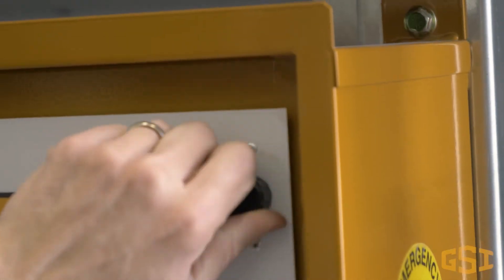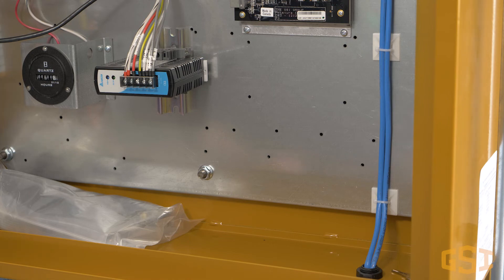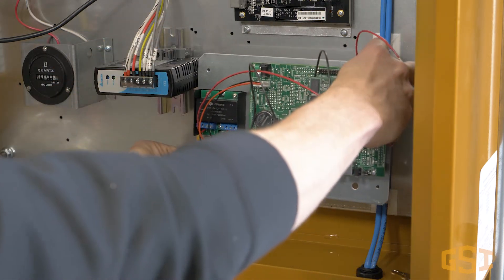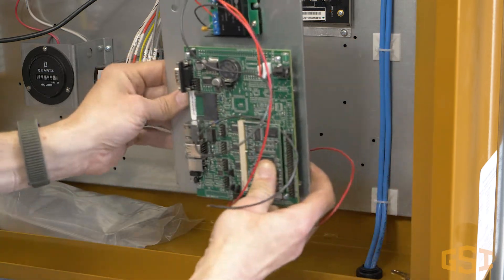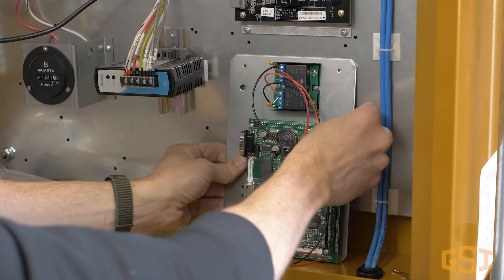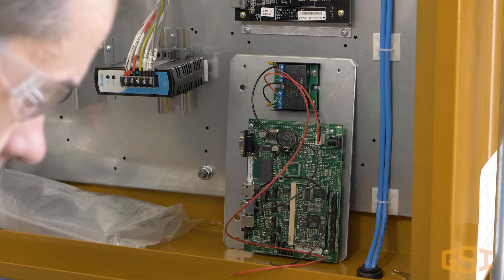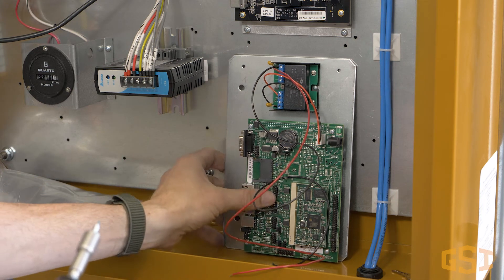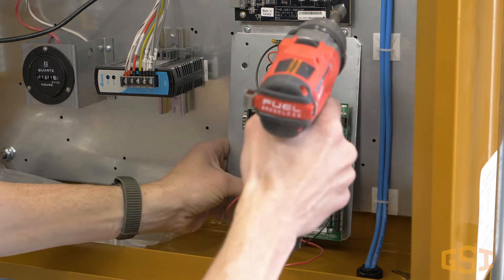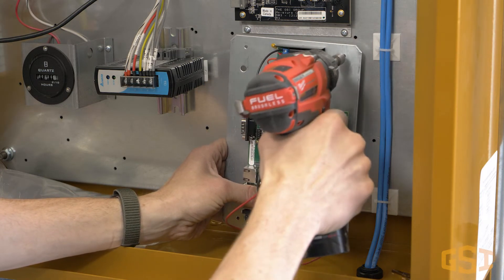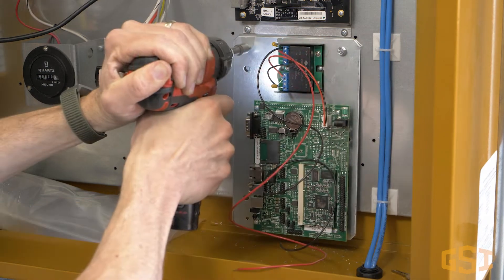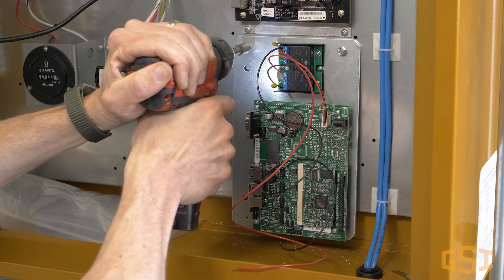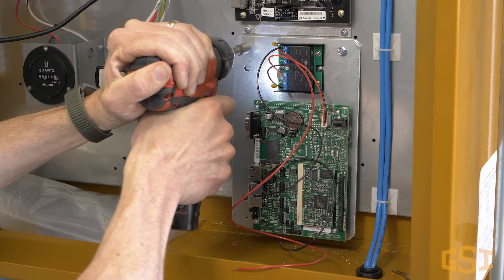Now that you're inside the control panel, let's identify a mounting location. There are a few things to consider. The mounting plate for the Watchdog circuit board measures 6 inches by 9 inches. When choosing the mounting location, remember that the communications cable must connect the circuit board to the display I.O. located on the front panel behind the display. Mounting the board is a simple process and only requires self-tapping screws that are included with the kit. Use the mount as a template for screw locations and then install the mount. You will need a drill or screw gun for the self-tapping screws.